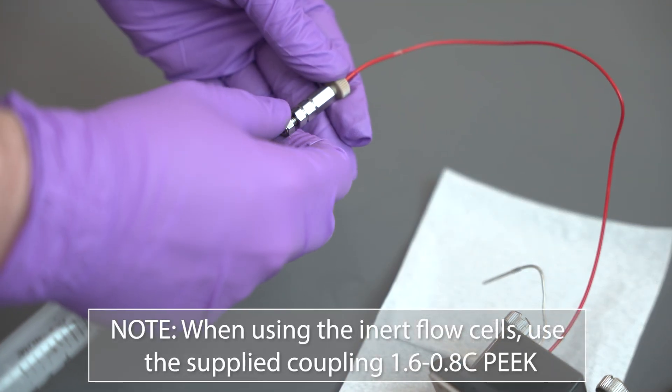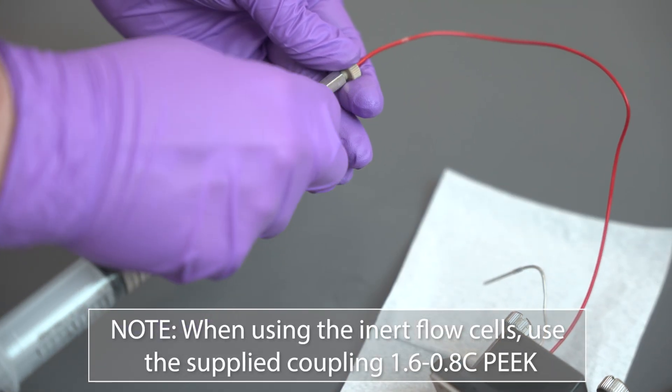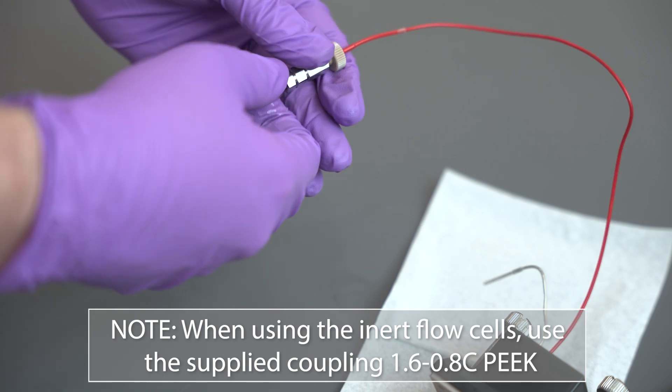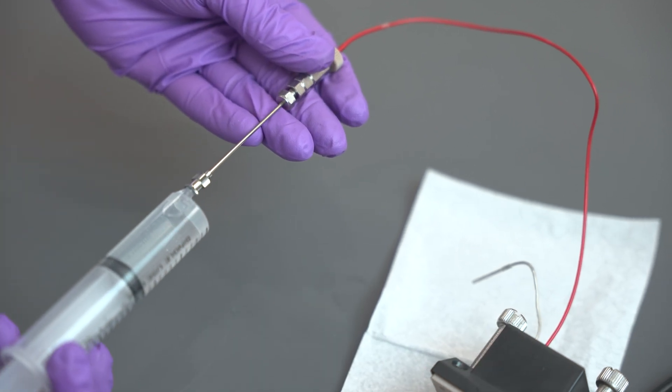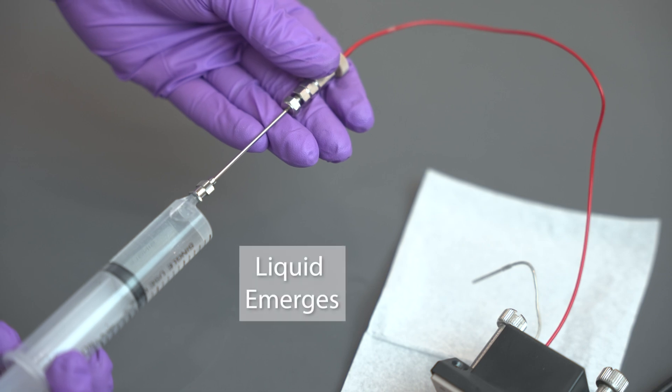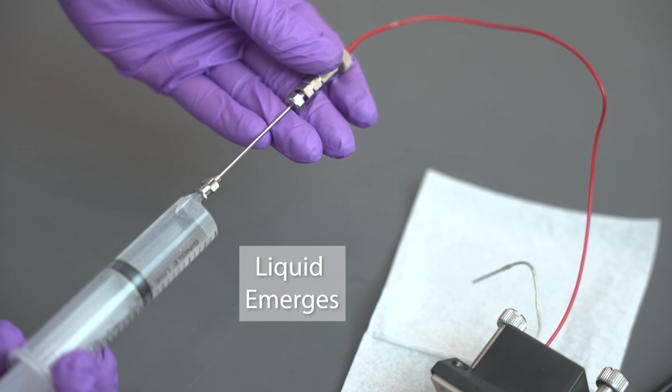When using the inert flow cells, use the supplied coupling 1.6-0.8C PEEK. Push 2-propanol through the flow cell slowly until you see liquid emerging from the outlet tubing.